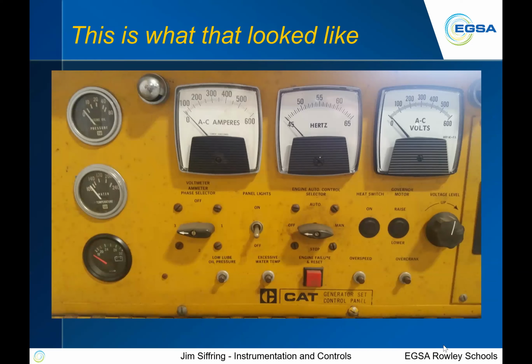Over in the lower left, we have a battery voltage meter. We don't have to have that. It's a nice feature, but we certainly don't have to have it according to NFPA. You've got the amp meters, the hertz or frequency meter, and the AC voltage meters up on the top. The switching in the middle will switch between those different devices. Then you actually have a 4-position switch here, which will give you the manual, off, and auto positions, as well as the stop position on this particular one. And on the far right, you have the voltage level rheostat, which will give you your plus or minus 5%. So this meets the minimum requirements, plus it has a few little features that you don't necessarily have to have. But even as old tech and old school as this thing looks, it meets all those parameters.